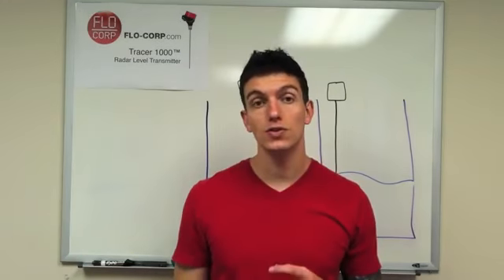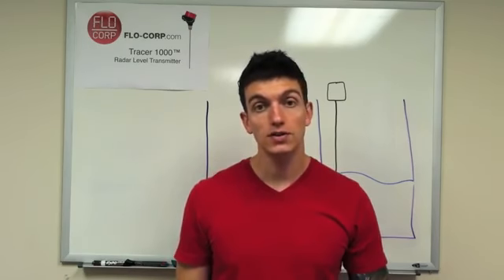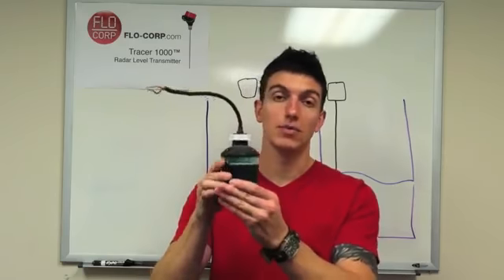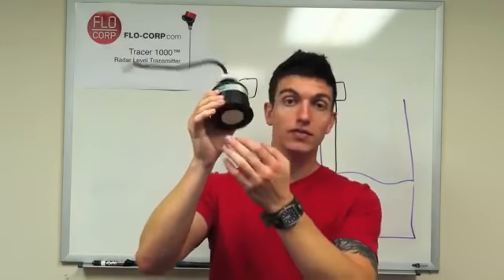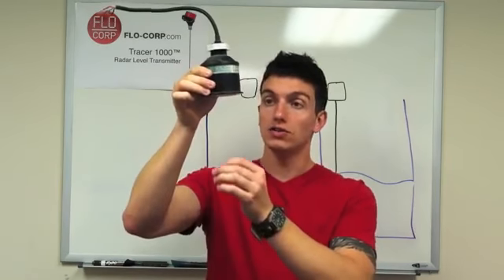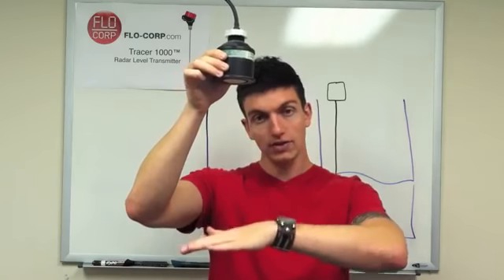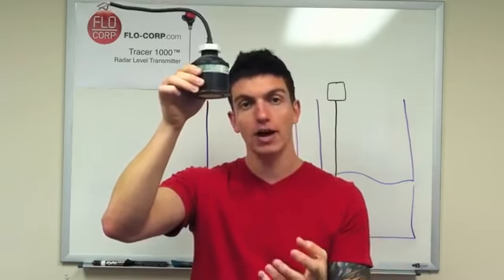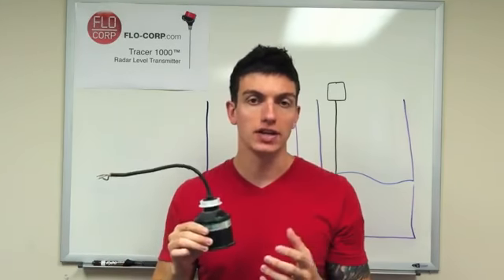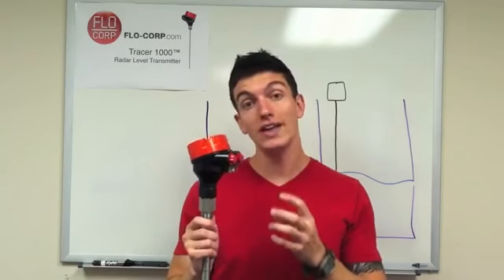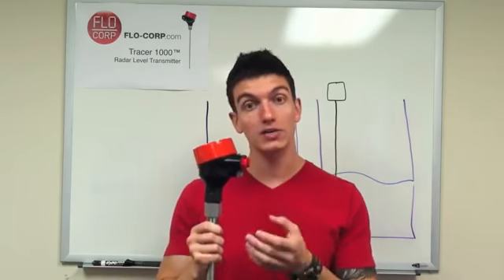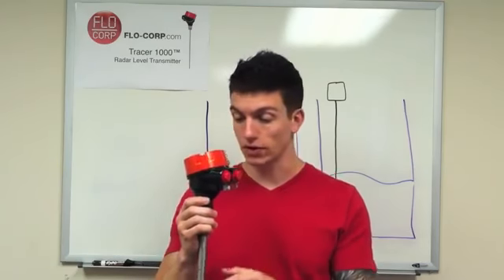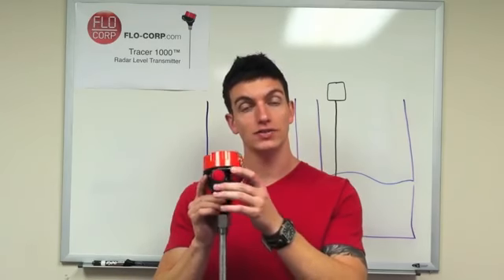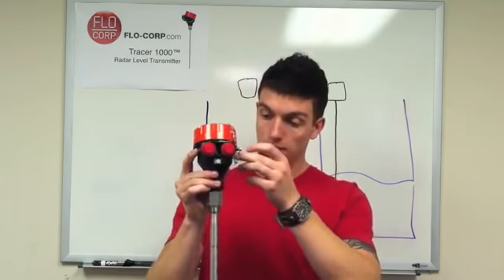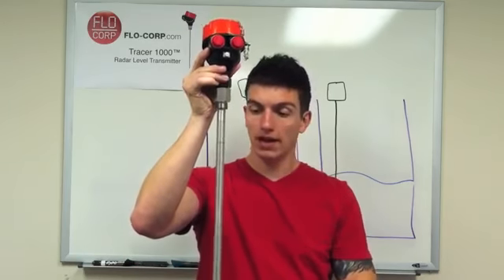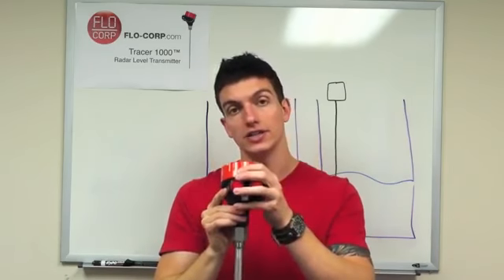Okay, I want to take a minute to show you an example of each of these devices. First, an ultrasonic level transducer. Essentially, the driver is on the bottom here, and the ultrasonic sound energy is transmitted from the driver down to the surface of what we're measuring, and using time of flight, which we just talked about, it will return, and that's how we get our level calculation. This is an example of a radar level meter, and specifically a guided wave radar level meter, which is what we're comparing in this tutorial. Essentially, this works in a similar way to the ultrasonic transducer. The microwaves are sent through the feed-through, down the probe, and then the return signal comes up, and that's how we get a level calculation.